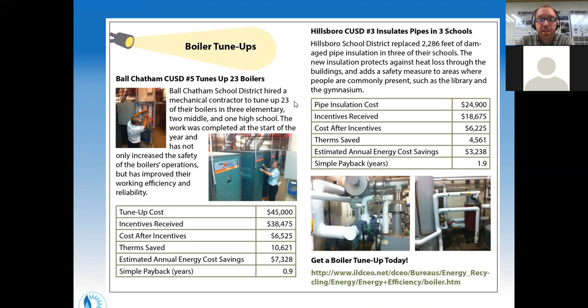In this example, they tuned up 23 boilers across 3 elementary schools and middle and high schools. The cost was $45,000 for this district to do this boiler tune-up program, but after incentives, it was only $6,000. They're saving $7,000 a year, so that's less than a one-year simple payback for return on investment.